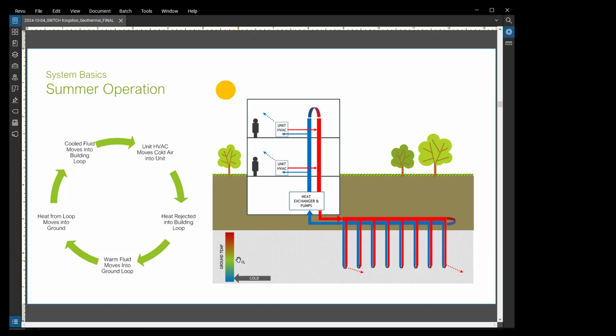So that heat is coming out of the space and going into the liquid, and because the loop is going in the same direction the whole way through, now the liquid that goes into the ground is warmer than the ground temperature. So it goes through the ground and then it will disperse back into the ground. And then your earth temperature that was colder will now raise back up by the end of the summer. And the whole process of the design, where you're considering how big your field is, how deep it is, how many HVAC units you have, all the various components, is trying to balance the amount of heat that's taken from the ground in the winter with the amount of heat that's put back in at the end of the summer.